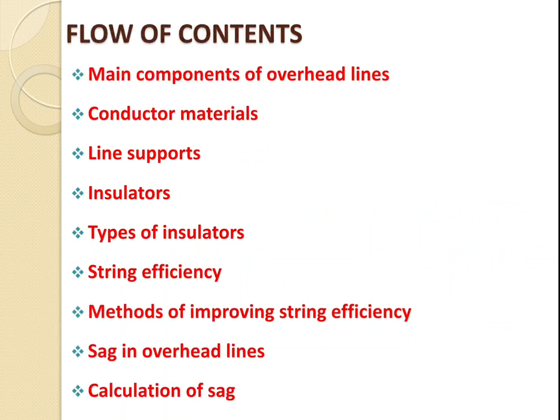So already we have discussed that the voltage applied across the string of the suspension insulator is not uniform due to the presence of shunt capacitance. The disc nearest to the conductor has a much higher potential than the other discs. The unequal potential distribution is undesirable and is expressed in terms of string efficiency.